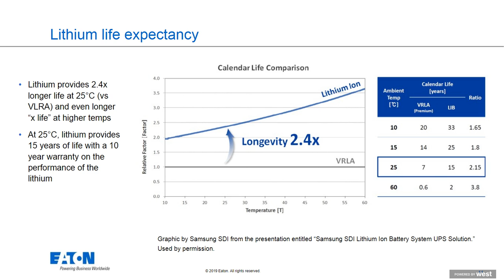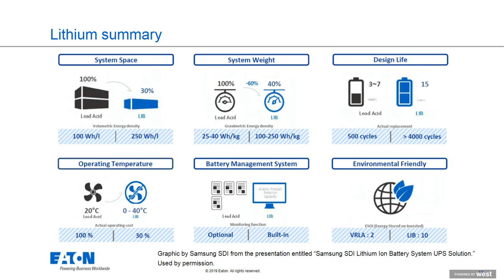Keep those things in mind as you look at literature from any of us vendors. In general though, with smaller size, lighter weight, better design life, and increased operating temperature range, you'll get better performance from a lithium battery. They always come with battery management systems that are more than just monitoring—they provide control over that battery cabinet or string, up to and including disconnecting it automatically and autonomously if something is trending in the wrong direction, even with no one there to take action. Its environmental friendliness is also usually calculated to be quite a bit better versus traditional lead-acid batteries.